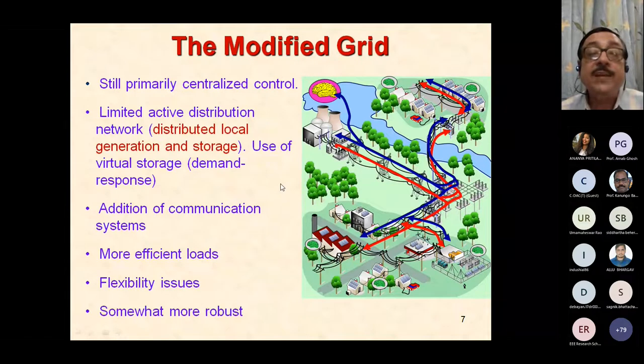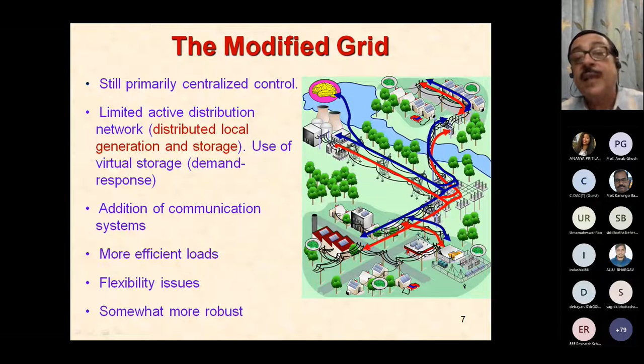What we are trying to do right now is to modify the grid so that we bring in certain local distributed generation at local points along with storages, perhaps storages everywhere it is not there, but that's our attempt right at the moment. We are trying to bring in distributed local generation and storage. So from here, we bring in something here. From here also, we can bring some power here. The advantage of providing local power generation on the distribution network is that the power has to flow over a shorter distance. So the line drops, the line losses are much reduced, and they are able to stabilize the voltage.